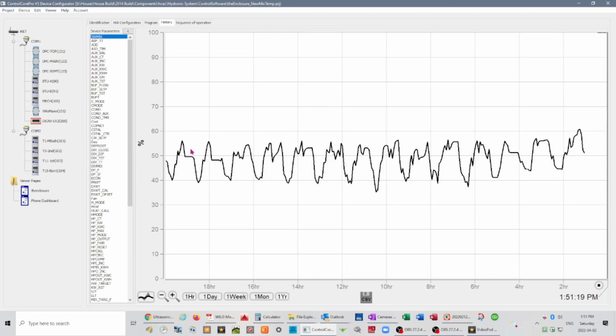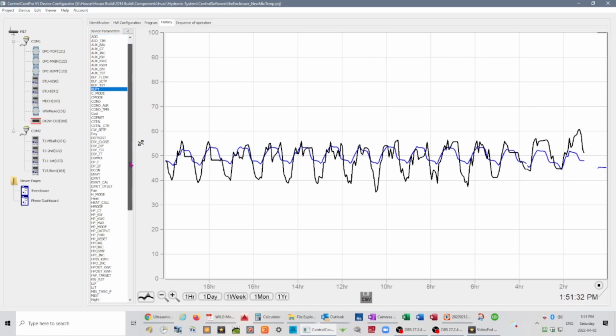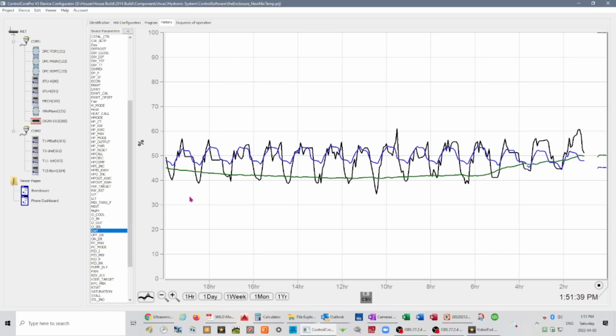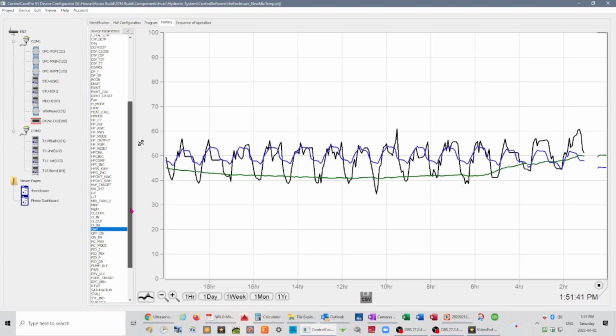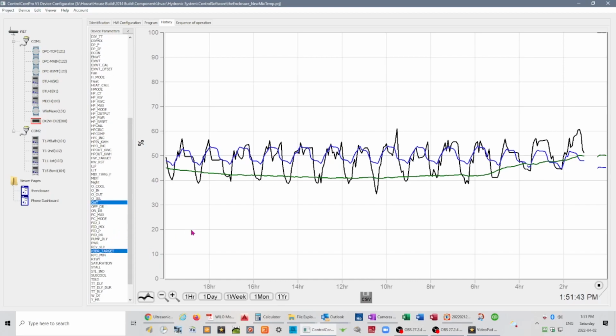But let's get to what I was trying to show you. That's the opening and closing of the mixing valve, buffer tank temperature. So you can see it cycles on and off based on the heat pump coming on and off. Let's add in our outdoor temperature. And then let's add in the target temperature based on the formulas that I've just showed you. And now let's add in the actual mixed temperature.